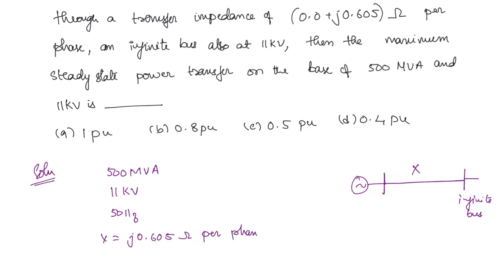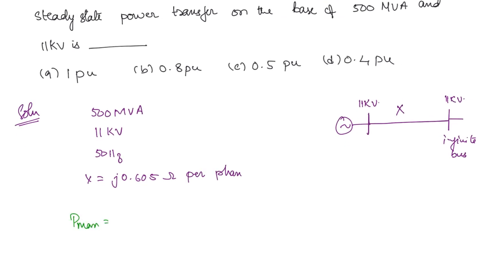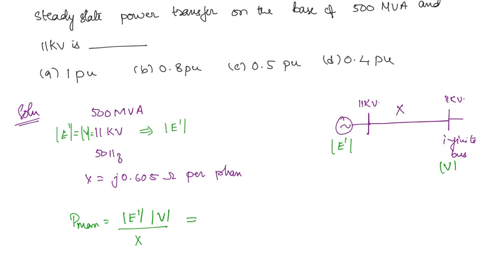Remember, 0.605 ohms is the per-phase value. Since both the generator voltage E and the infinite bus voltage V are at 11 kV, and we want values on the 11 kV base, both E and V in per unit equal 1 per unit. We also need to find X in per unit.